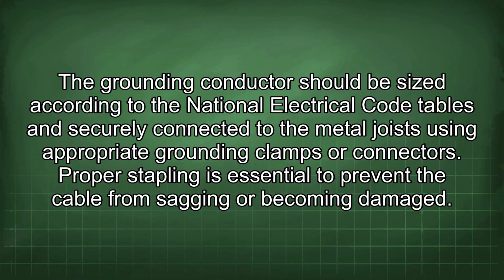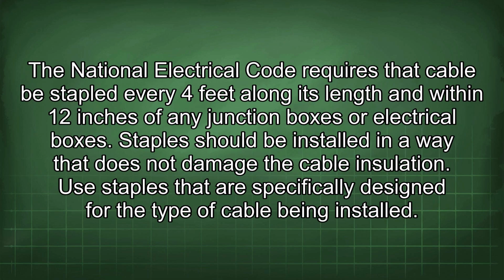Proper stapling is essential to prevent the cable from sagging or becoming damaged. The National Electrical Code requires that cable be stapled every 4 feet along its length and within 12 inches of any junction boxes or electrical boxes. Staples should be installed in a way that does not damage the cable insulation. Use staples that are specifically designed for the type of cable being installed.